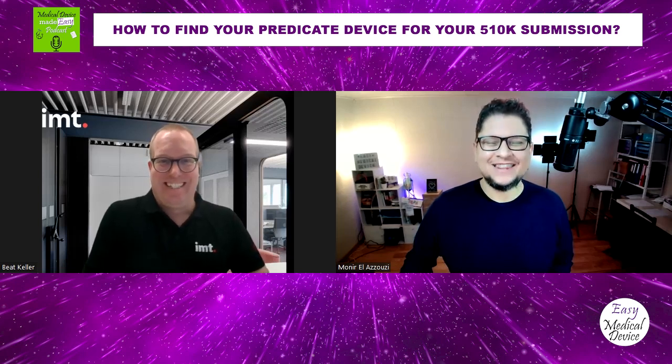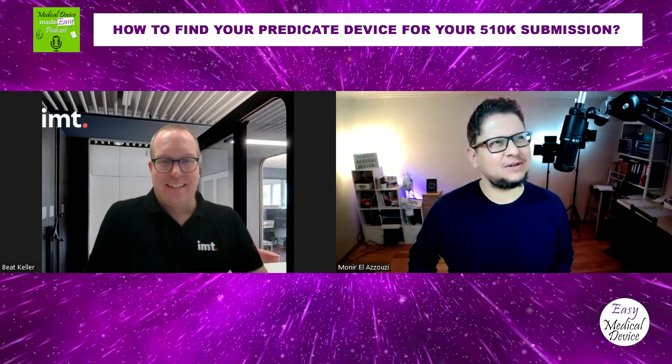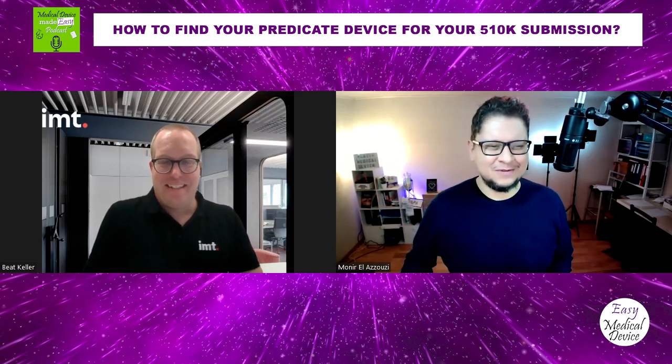Exactly. Which is the correct term in the US. Yeah, there is a difference with clearance. What is the other term? Because there are different terms that you can use for that. Yeah, but for the 510K, it's a clearance, and the PMA is an approval. Exactly. People are sometimes misusing those terms. There is no registering or licensing, whatever is seen out there on the internet. It's a PMA approval or a 510K clearance.